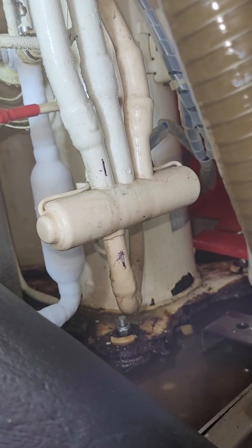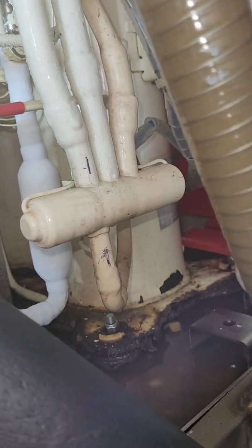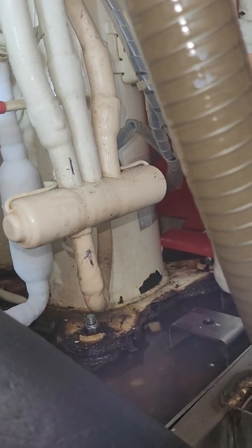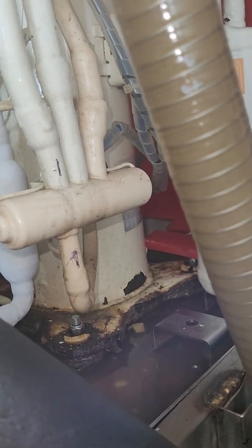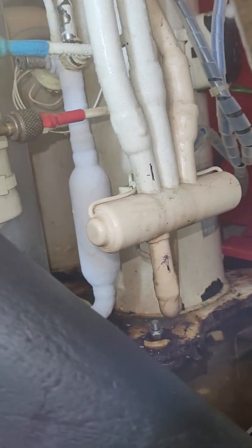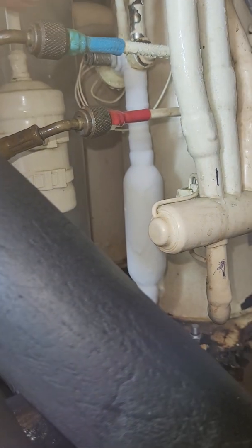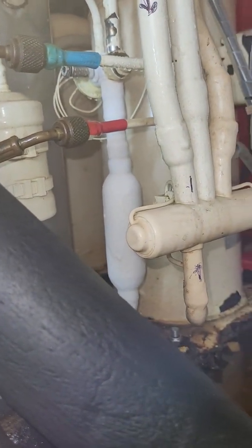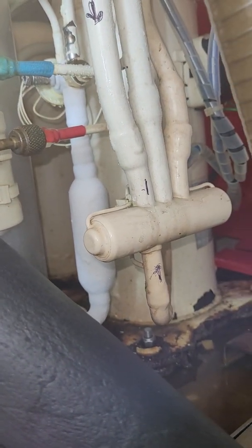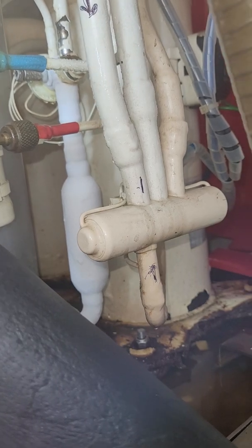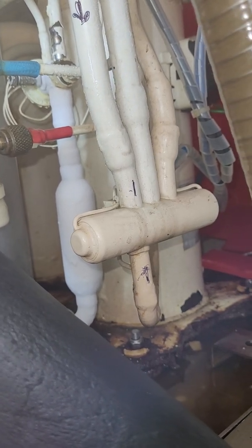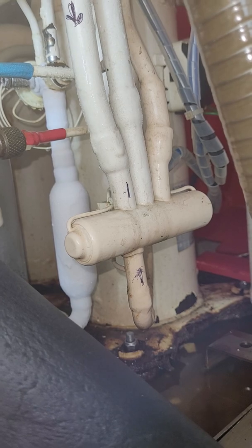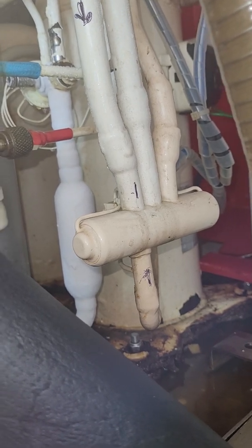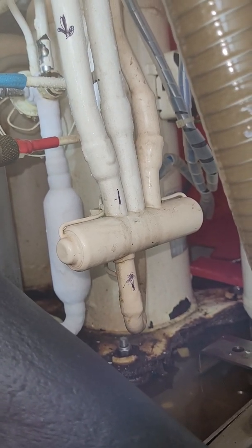So if it gets overheated, the varnish on those windings will give a very distinctive burned smell. So by letting out a little bit of oil and smelling it, you can pretty much see whether this compressor has overheated or burned out. If it burned out, you will actually see the oil being very dark and dirty, and obviously it will have this distinct burnt plastic kind of smell.